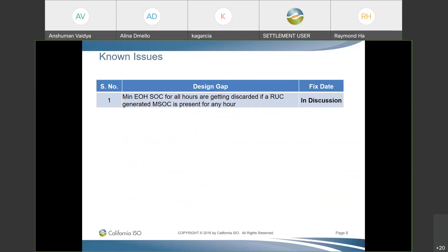Yesterday we identified a design gap for ESDER-04, where minimum end-of-hour state of charge (EOH SOC) for all hours are being discarded if a RUC-generated MSOC is present for any hour. So if you have any MSOC present — for, say, interval 1 or interval 2 — it will discard all minimum EOH SOC values for all hours of that day. We identified this design gap yesterday, and it is being discussed internally with our team.